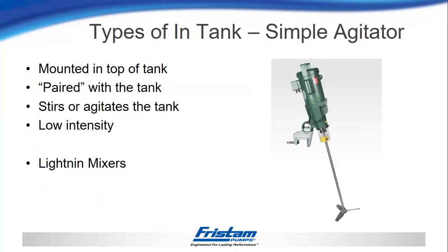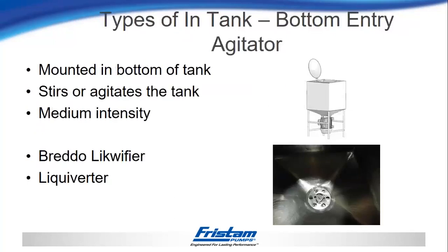I would consider this type of agitator to be low-intensity — it's basically like a slow stir. The next type is a bottom entry agitator, typically something like a liquefier, a Breddo Likwifier, or a Liquiverter. This is mounted to the bottom of the tank, and just the mix head comes straight through to stir and agitate the tank. I would consider this more of a medium intensity — it runs at a higher RPM, but it doesn't have a rotor and stator set up to give you really high shear.